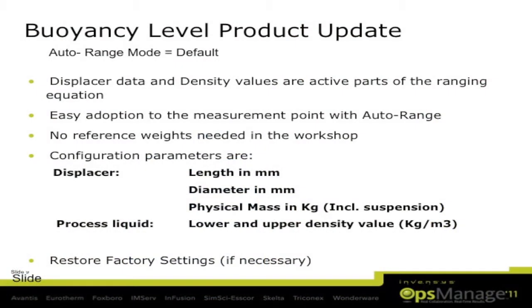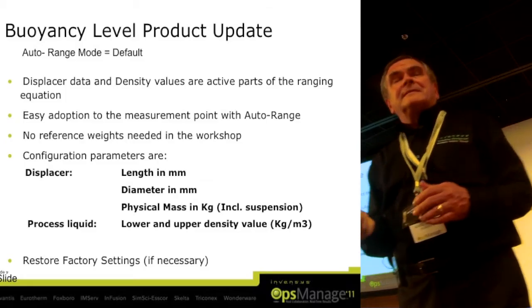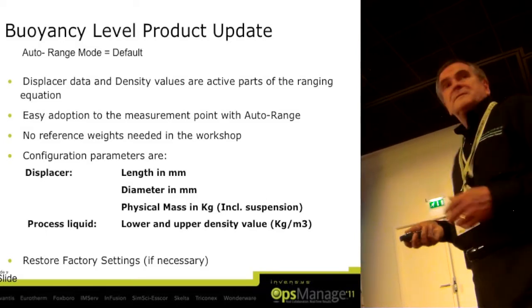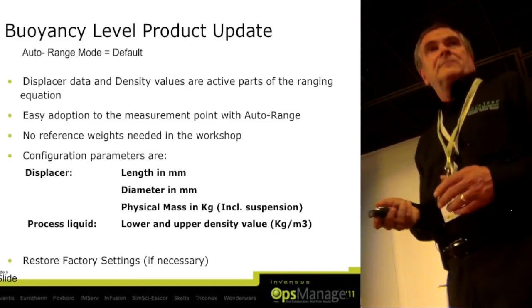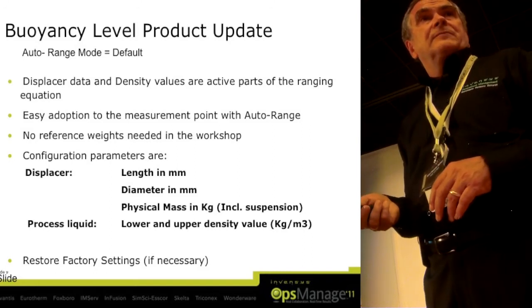Then also very important and very new is the auto range mode of this transmitter. Auto range mode is the default setting. So the displacer data and the density value are an active part of the equation. This was not the case in the past. Here with the new electronics we can do this. So there's an easy adaptation to the measurement point with auto range. No reference weights are needed. So it's absolutely not necessary in the field to operate with weights, to calibrate or to rearrange the transmitter. The configuration parameters are the displacer data, the length, the diameter, and the physical mass in kilograms, and the process liquid, the upper and the lower density of the liquid.